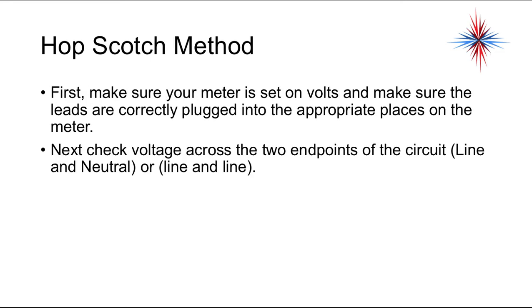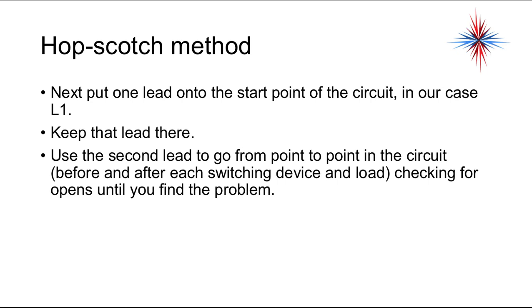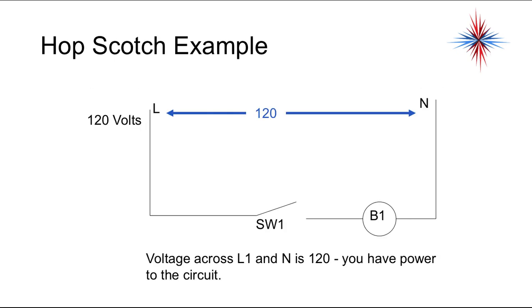First, make sure your meter is set on volts and make sure the leads are correctly plugged into the appropriate places on the meter. Next, check voltage across the two endpoints of a circuit, line and neutral or line and line. Put one lead on the start point of the circuit, or in our case L1. Keep that lead there. Use the second lead to go from point to point in the circuit before and after each switching device and load and check for opens until you find the problem.